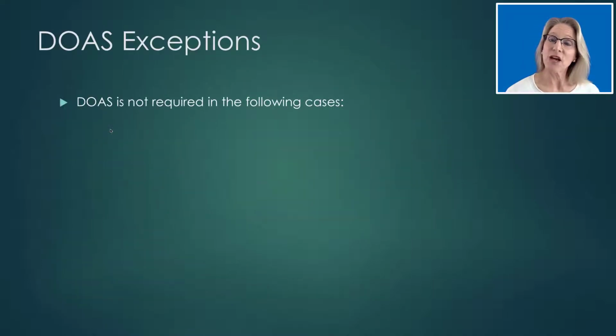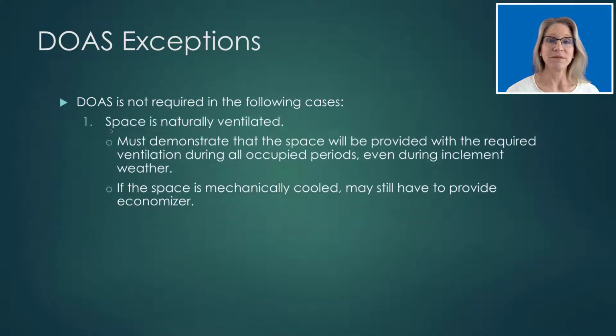Now, there are 2 cases when a space that would normally be required to be served by a DOAS may avoid this requirement. The first one is if the space is going to be naturally ventilated. Do note that if that's the plan, you do need to demonstrate that the space will be provided with the required ventilation air during all occupied periods, even during inclement weather. We actually receive quite a few questions about that particular detail, and jurisdictions do want to verify that. And also, if the space is mechanically cooled, you may still have to provide economizer, so do look into that detail as well.